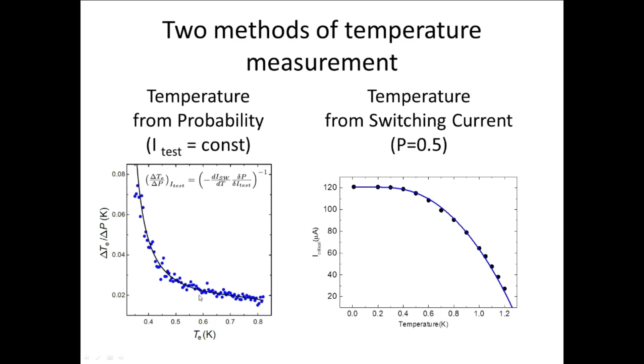Here I plotted the inverse of the temperature responsivity. On the other hand, we can fix the value of the switching probability, say at the 1/2 value, and then we can measure the switching current corresponding to this probability, and this gives us another way of temperature determination. So here we have two calibration curves. Here is the switching current corresponding to temperature, and here we have responsivity corresponding to temperature.